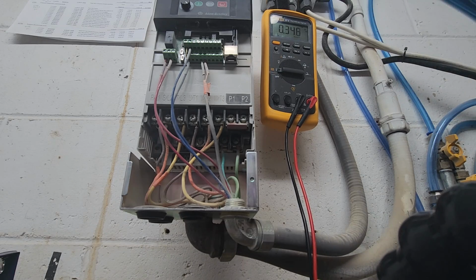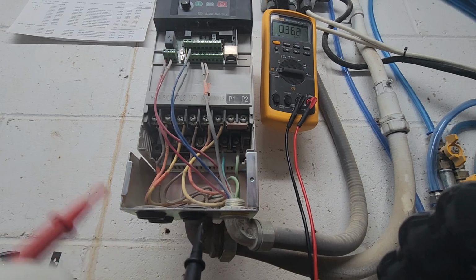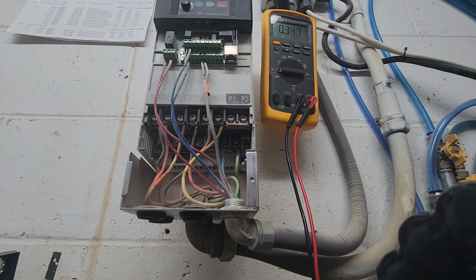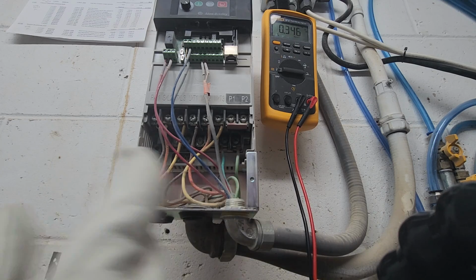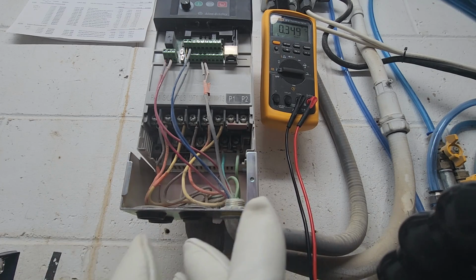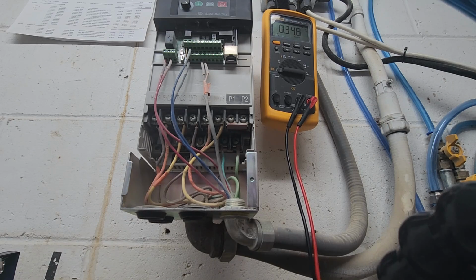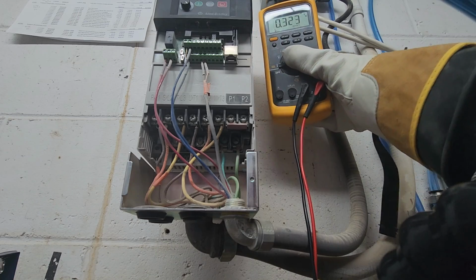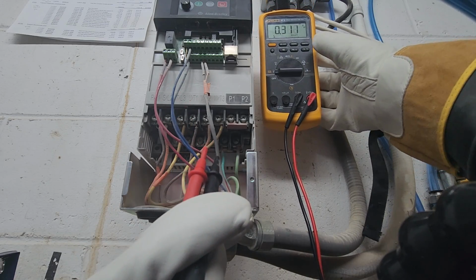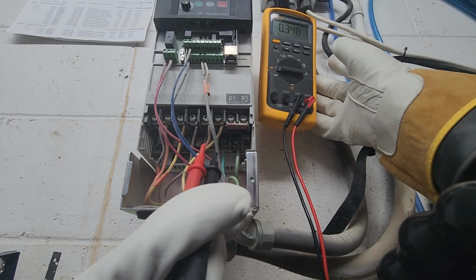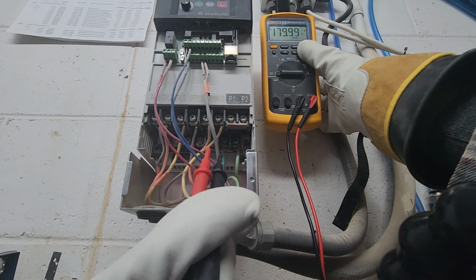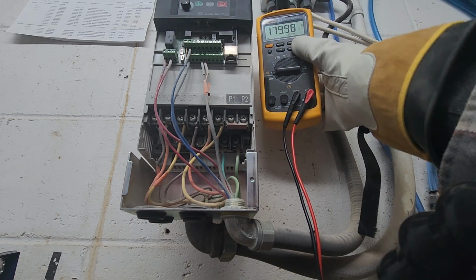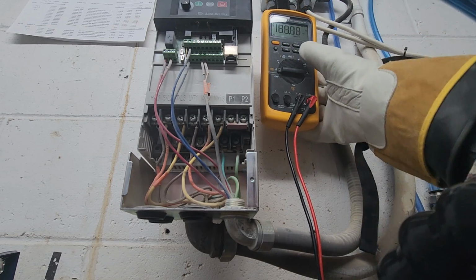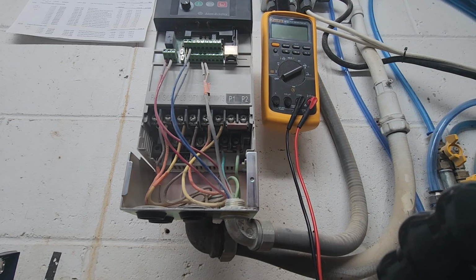And then the other thing we can do is go from output to output, so T1 to T2, 1 to 3, or 2 to 3, and check our frequency. You also need to use a low pass filter to check your frequency, otherwise it'll be reading all of your pulses and it'll say something ridiculous like 20,000 hertz, even though your VFD is actually running at 30 hertz or 35 hertz or whatever. So you need to stick it on the Fluke 87 V, you go into volts, you take your voltage reading on your VFD, and then you hit your low pass filter. So you've got your low pass voltage reading, and then you hit your frequency button, and that'll pull up your frequency through the low pass filter, giving you the accurate reading of what the VFD is trying to give your motor.